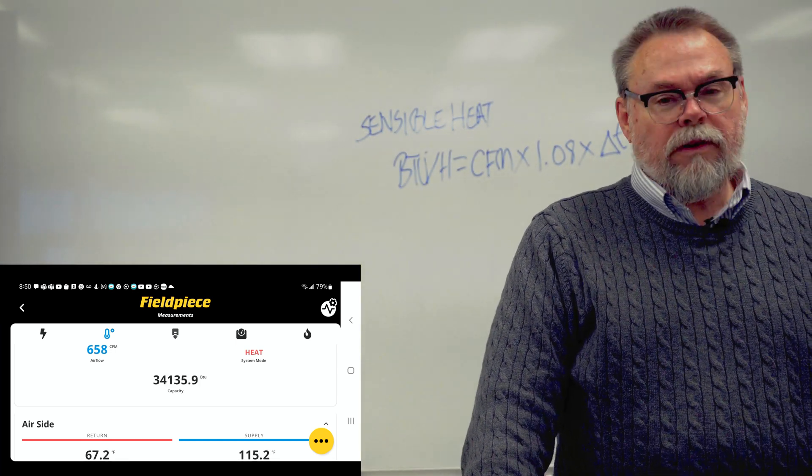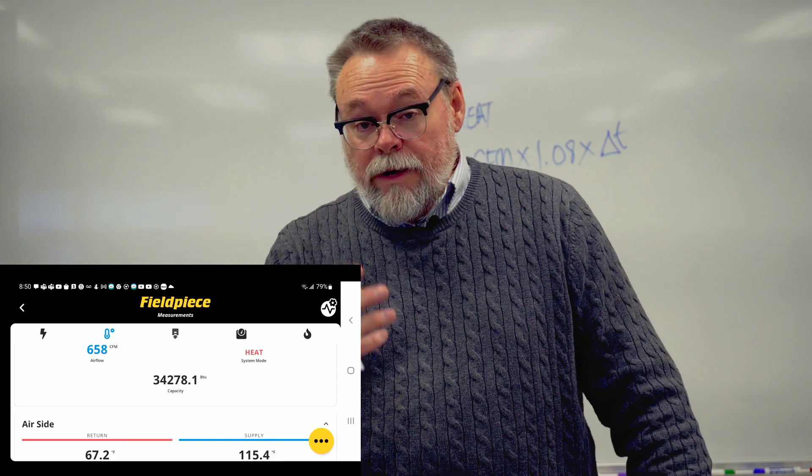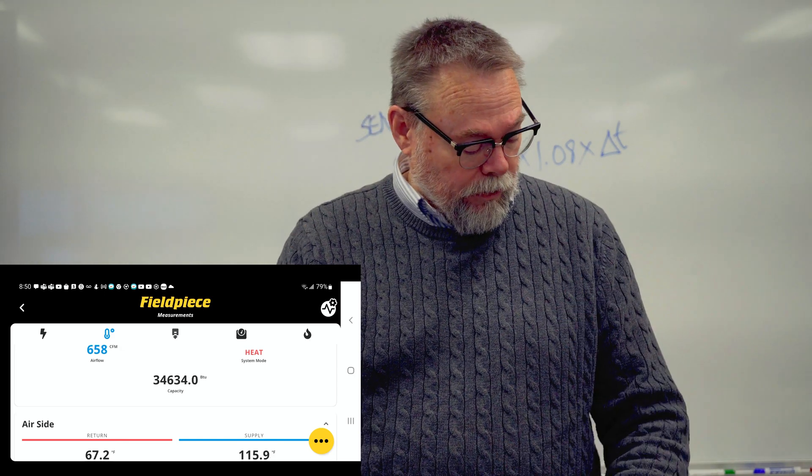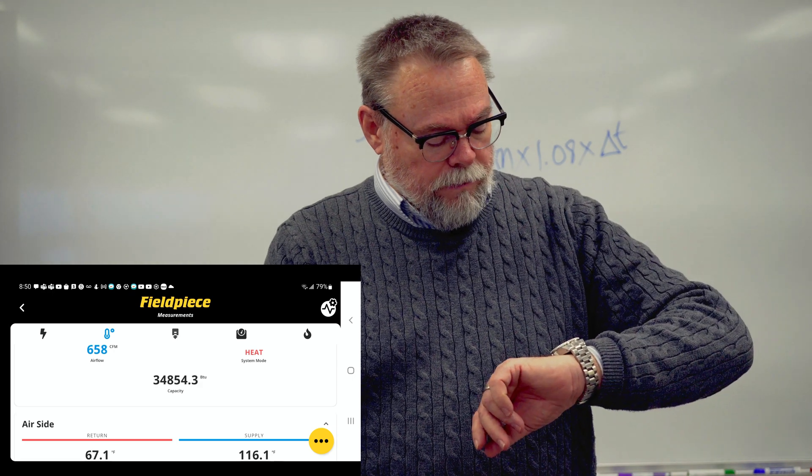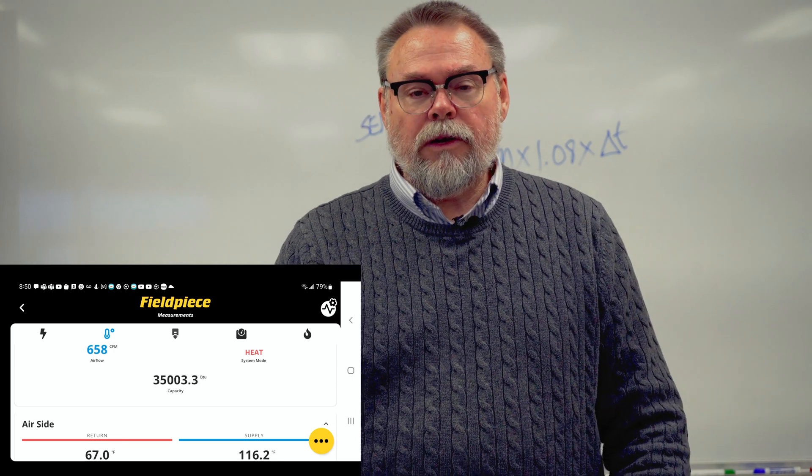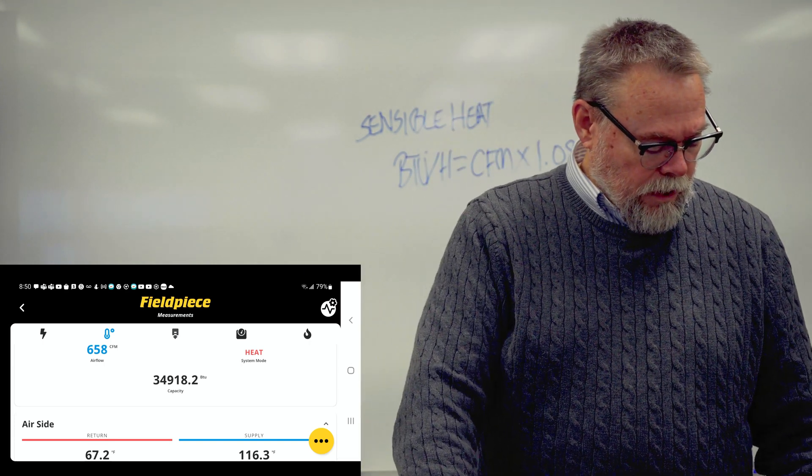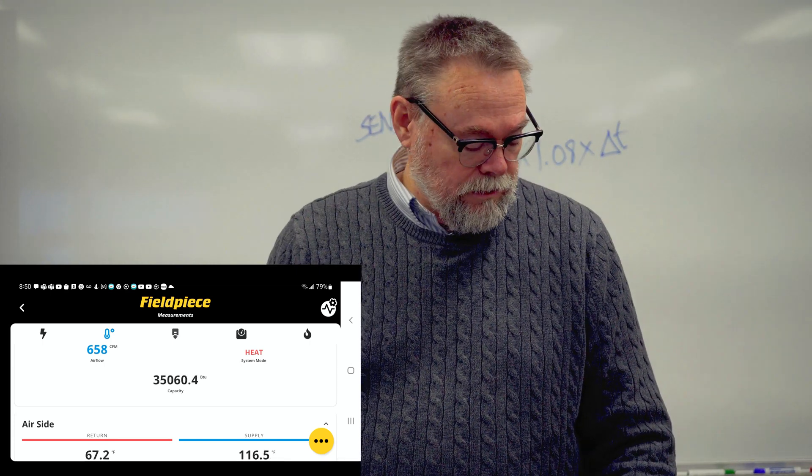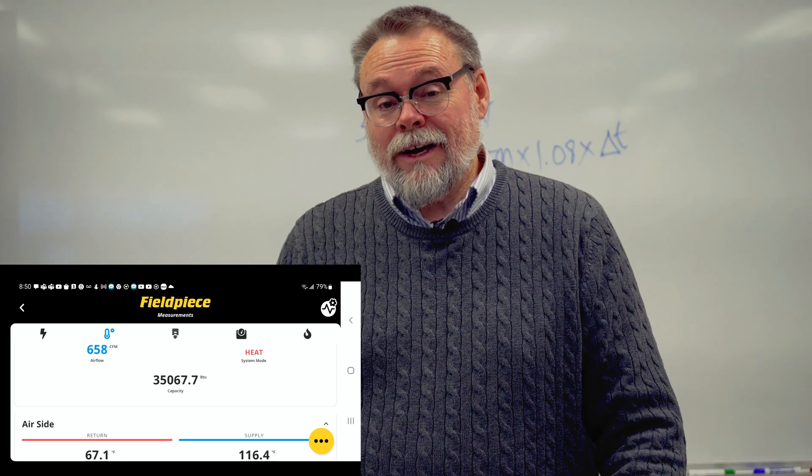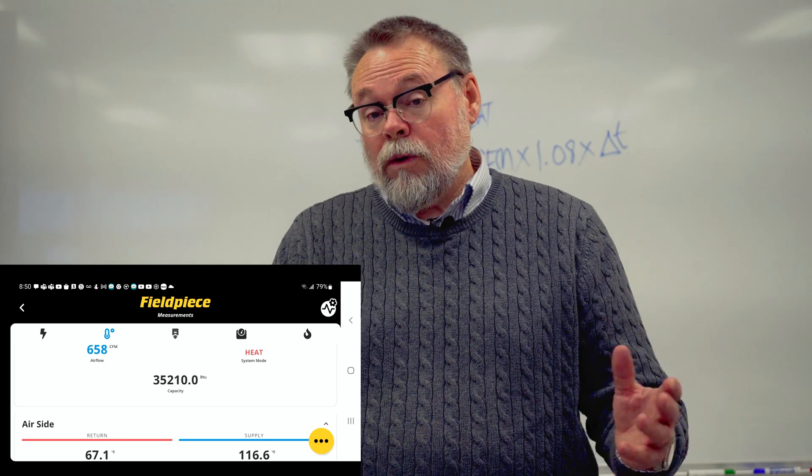Our BTUs jumped up. We're at 34,000 and climbing. So we're getting right where we're supposed to be. That's exactly what you want. We're coming up on nine minutes now. We'll give it another minute or two here. 34,008, 35,000. Looks like we're going to hit our 36,000, which is just perfect. That's exactly what we're supposed to be.